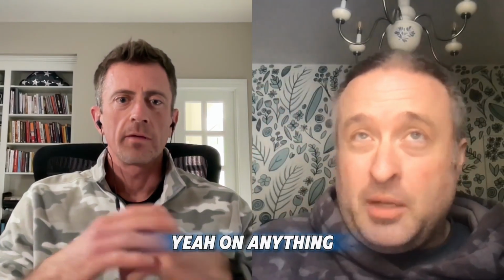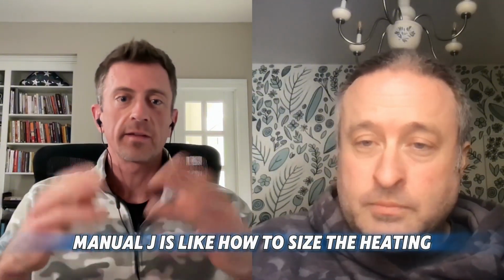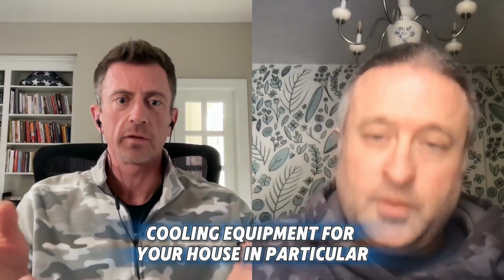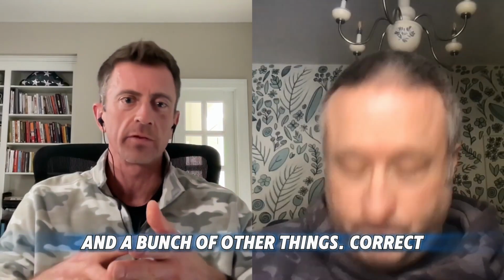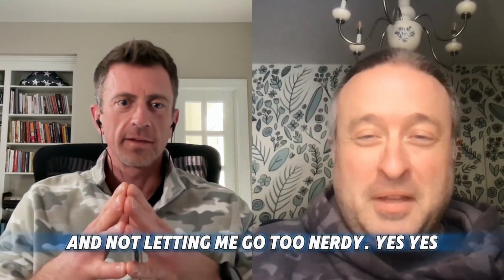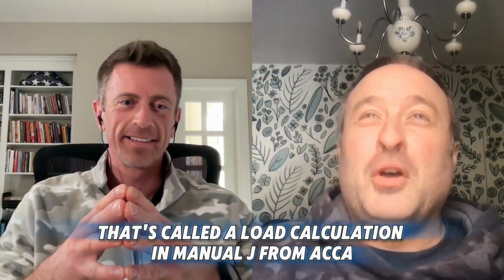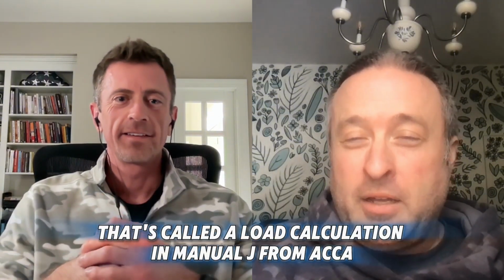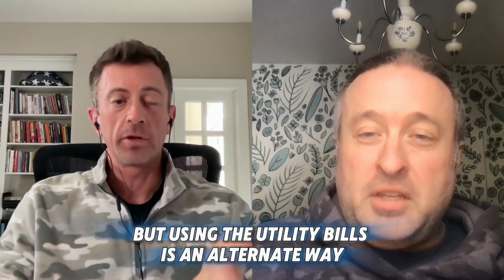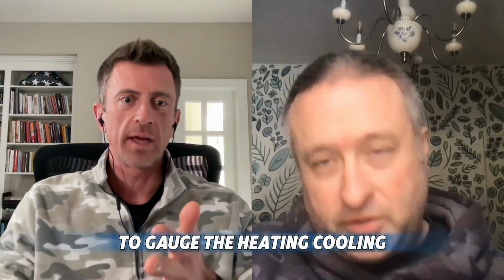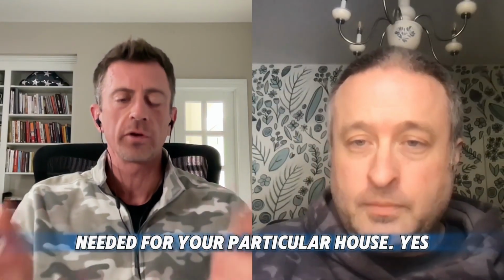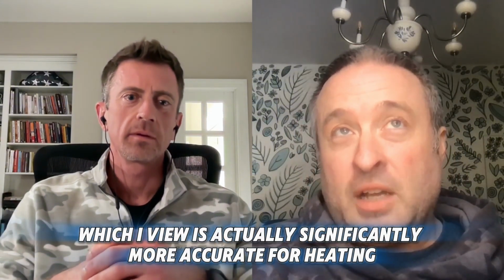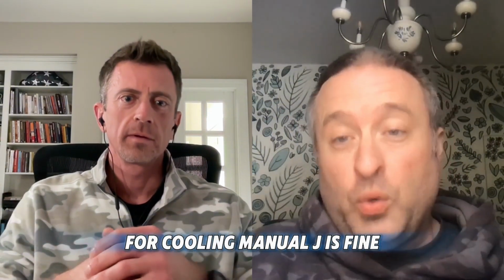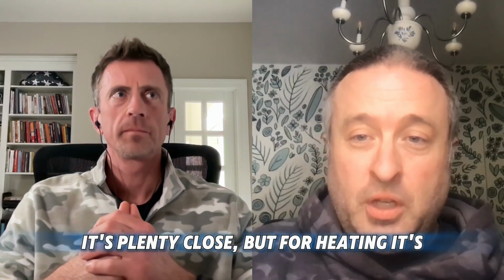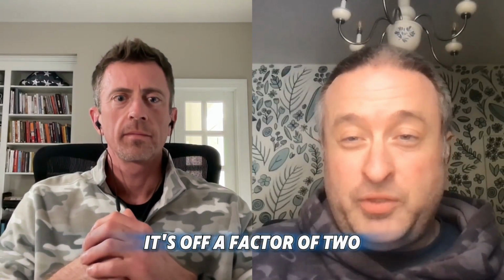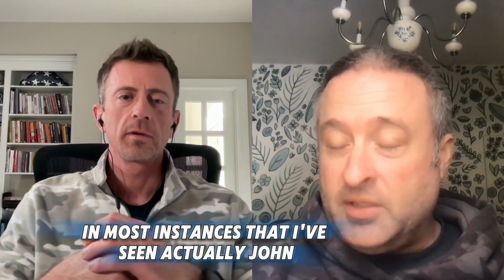Yeah. On anything. And so what you're talking about, Manual J, is like how to size the heating and cooling equipment for your house in particular, based on air leakage and insulation levels and a bunch of other things. Correct. Thank you for jumping in and not letting me go too nerdy. That's called a load calculation in Manual J from ACCA. It's the Air Conditioning Contractors of America. But using the utility bills as an alternate way to gauge the heating and cooling size of the equipment needed for your particular house. Yes, which I view as actually significantly more accurate for heating. For cooling, Manual J is fine. It's plenty close. But for heating, it's off by a factor of 2 in most instances that I've seen.